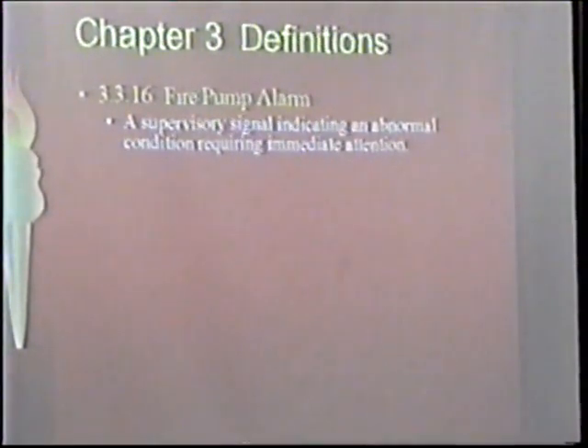This was another definition that wasn't in the code book before, that I don't think we saw in there. Which is describing what a fire pump alarm is. It's a supervisory signal requiring immediate action. And I think the point here, at least how we interpret it, was that it's not a fire alarm, it's not required to have trucks responding to a fire pump alarm. I know some cities do require that.